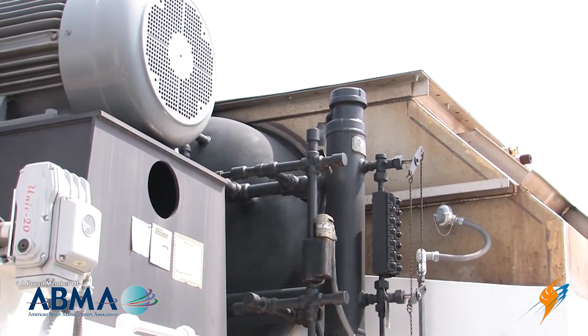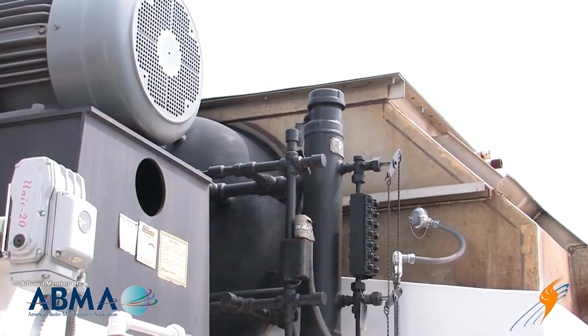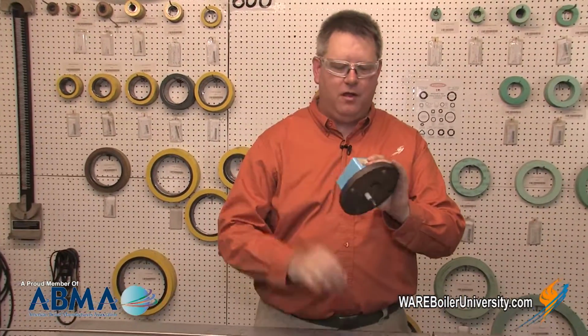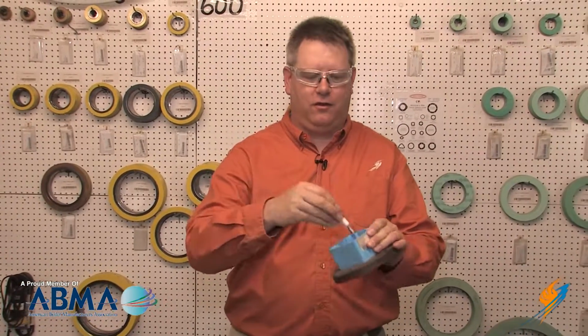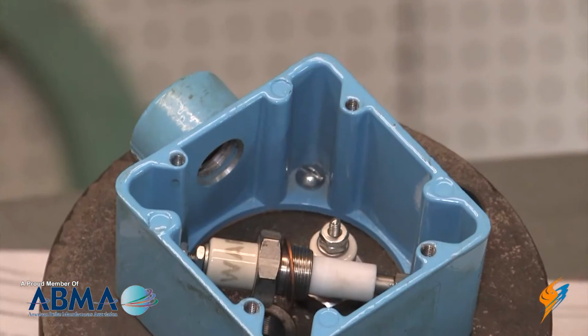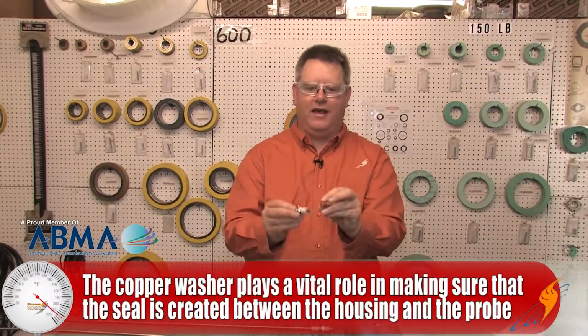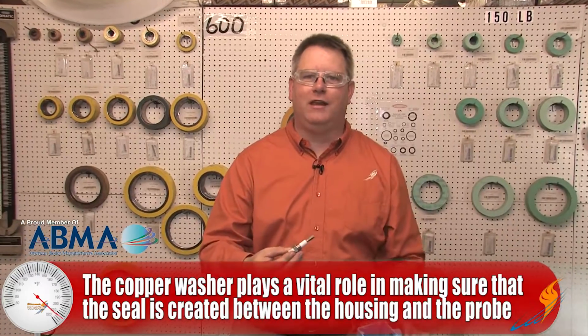Another example is housing mounted on the center line of the boiler, and you can also put multiple probes in an external pot, as you would frequently see on a water tube boiler. Let's take a look at some of the internal parts of the probe assemblies that we've been looking at. This is an example of the top housing. These have threaded inserts which the probes can be threaded into. An important part of assembling these is this copper washer, because that's what forms the mechanical seal to make it pressure tight. So don't lose your copper washer.